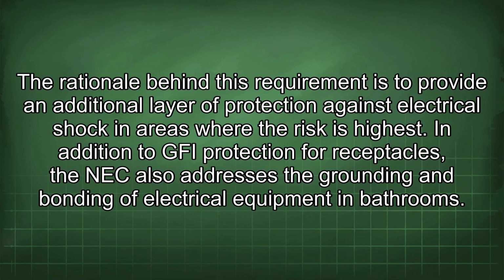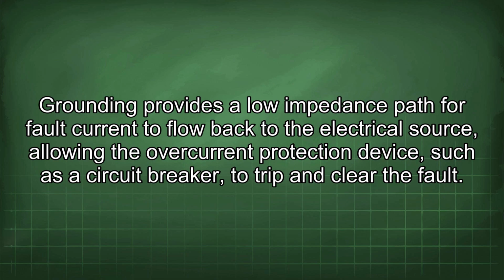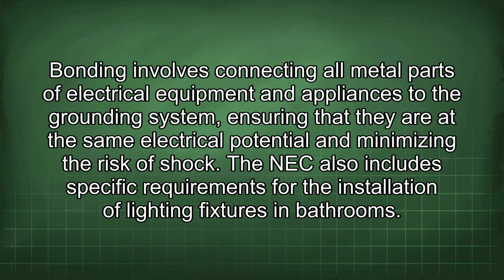In addition to GFI protection for receptacles, the NEC also addresses the grounding and bonding of electrical equipment in bathrooms. Grounding provides a low-impedance path for fault current to flow back to the electrical source, allowing the overcurrent protection device, such as a circuit breaker, to trip and clear the fault. Bonding involves connecting all metal parts of electrical equipment and appliances to the grounding system, ensuring that they are at the same electrical potential and minimizing the risk of shock.